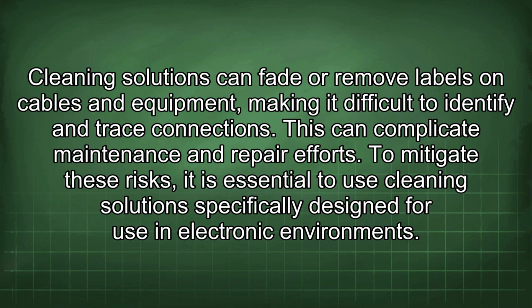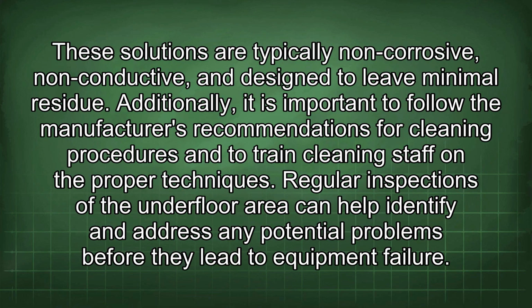To mitigate these risks, it is essential to use cleaning solutions specifically designed for use in electronic environments. These solutions are typically non-corrosive, non-conductive, and designed to leave minimal residue. Additionally, it is important to follow the manufacturer's recommendations for cleaning procedures and to train cleaning staff on the proper techniques.